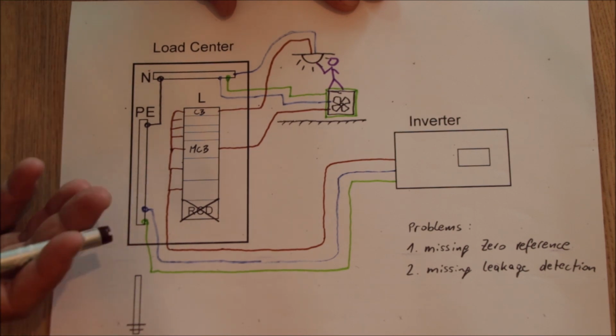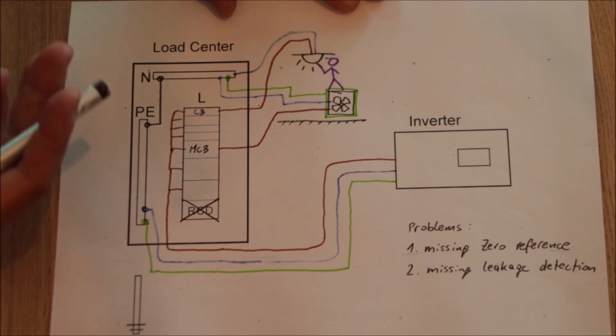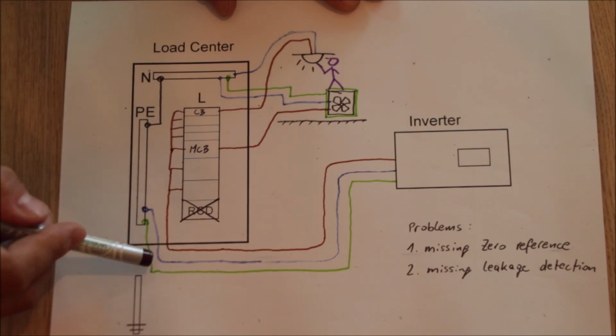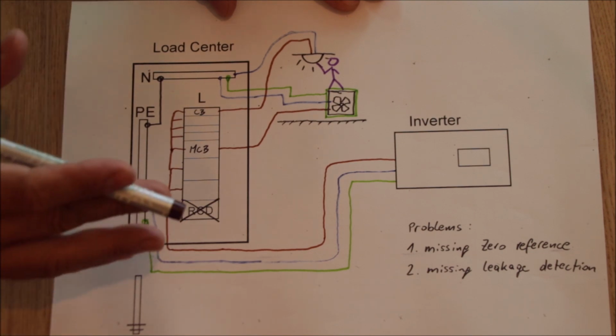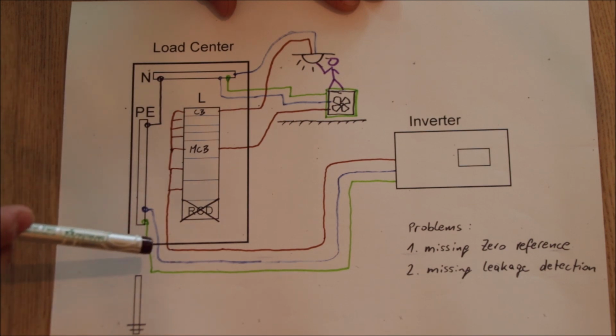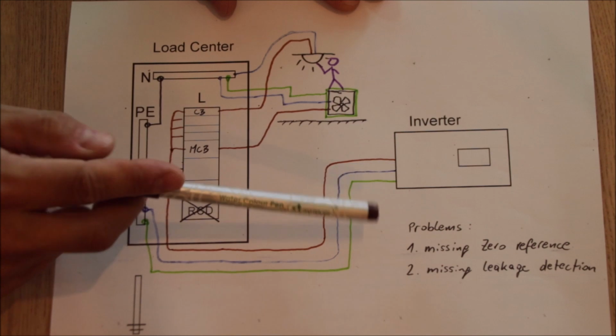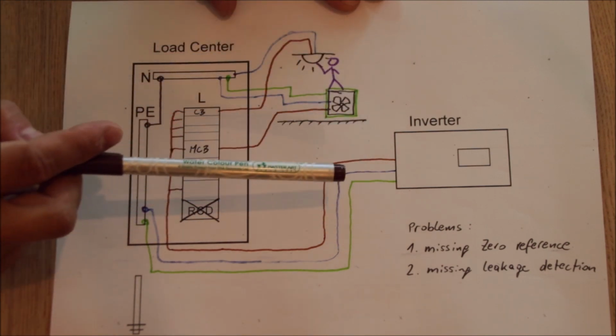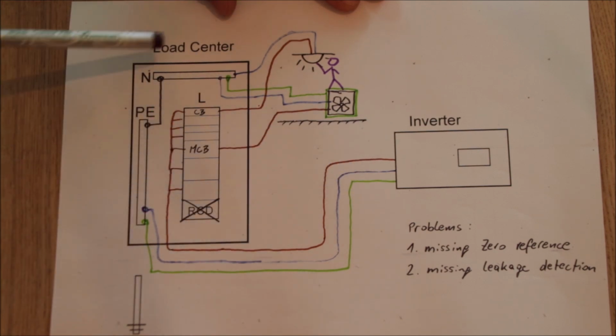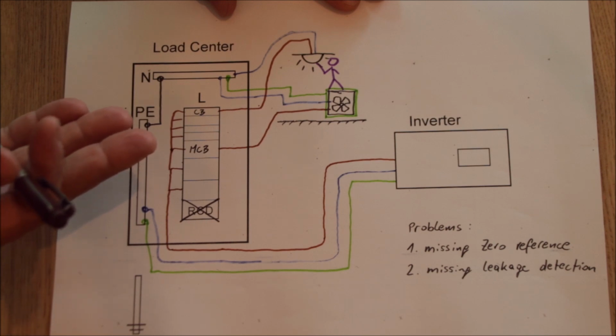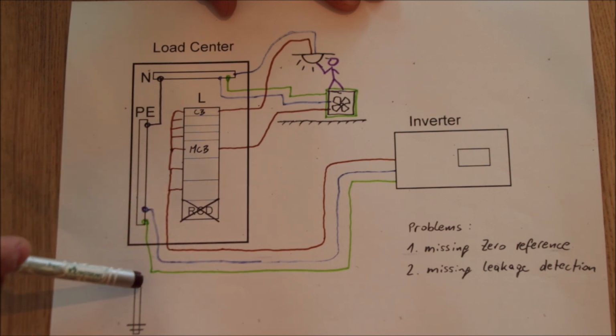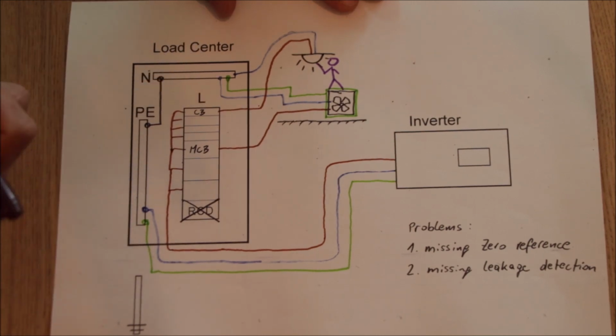So the bonding which you do is done for two reasons. First, you are getting reference to zero, reference to earth, integrated into your system, right? Because a setup like this is an IT system, as you know, an isolated earth throughout all of the system. So the neutral actually in this setup will be hot, because it is missing zero reference. So I'm pretty sure that if he measures between a point of earth and his neutral, there will be voltage on this. What can be the problem with that?